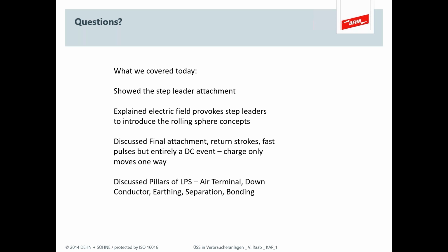Terrific questions, and those are actually really lengthy answers, dependent on your customer's applications, of course. Somebody like a power plant is going to want what looks like a big grid and rings and then strategic vertical earth rods, and a residential building might have a very simple ring and one or two rods. At my house I had one earth rod. It looked almost like a single rod, but all of my services were linked together, so I had everything bonded. Touch and step in a system like that is going to be really high because you've got everything concentrated in one rod, so your voltage gradients are really high in the soil, or in whatever your conditions are. So then treatment of things like concrete layers becomes really important.